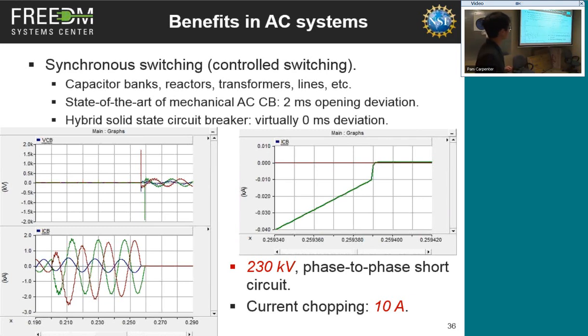I'll give you an example here. I did a simulation of a phase-to-phase short circuit, similar to before, but I put some current chopping level on the circuit breaker. Current chopping in AC circuit breakers means it does not actually wait for the real current zero to interrupt the arc. It has a tendency to interrupt at a moment very close to current zero.